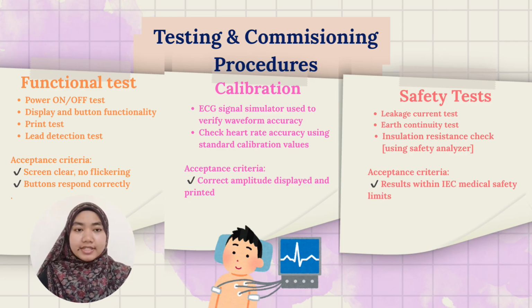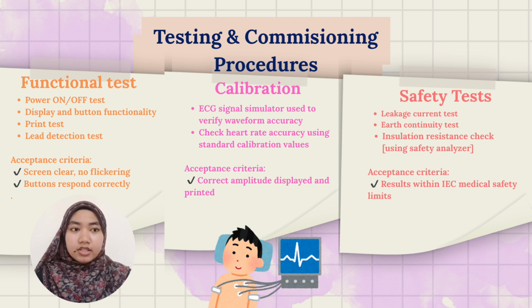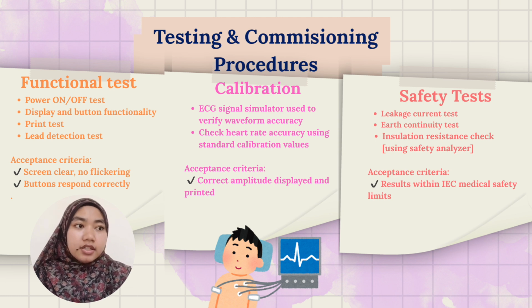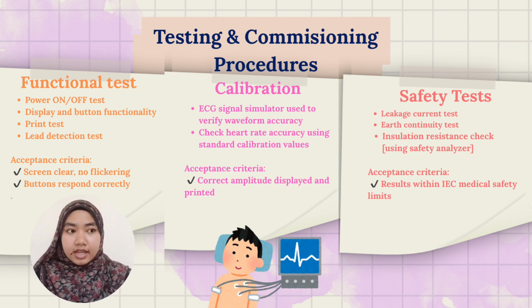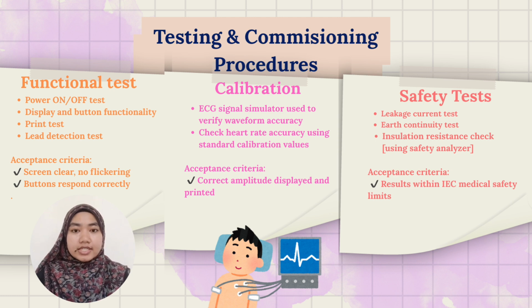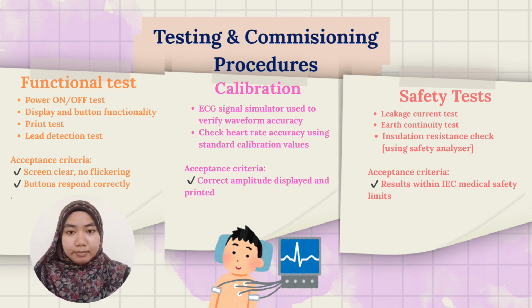Now let's move to the testing and commissioning procedure. First, the functional test: power on-off test, display and button functionality, print test, and lead detection test. The acceptance criteria are a clear screen, no flickering, and buttons responding correctly. For calibration, we use an ECG signal simulator to verify waveform accuracy and check heart rate accuracy using standard calibration values. The acceptance criteria are correct amplitude displayed and printed. The last one is the safety test: leakage current test, earth continuity test, and insulation resistance check, for which we use a safety analyzer. The acceptance criteria are within IEC medical safety limits.